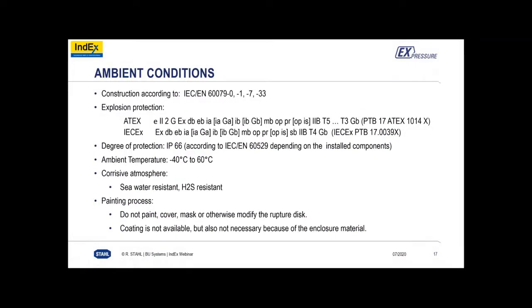So, ambient conditions, if I'll just cover this one really quickly. Construction, as we mentioned: the typical standards are 60079-1 for EXD and -33 for EXS. You do have the option for the connection chamber to -7, and it meets the general requirements of -0. As Kirgily mentioned, this is an IECEx and ATEX certified device. There are the certification numbers. We will share that in an email for you.